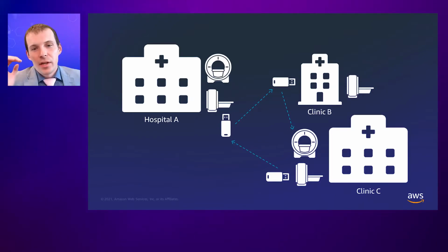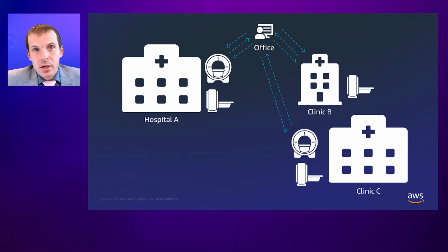Because of that large impediment of time, the threshold for me for making a change is actually pretty high. So we make fewer changes than we'd like to make because of this current situation. With the solution that Yaxi from GE just described, the need to physically go site to site, the need to stop that site from scanning patients because I need to get on the scanner to program it, and the need for that site to stop earning any revenue, those needs evaporate. I can sit in my office and manage all of these scanners as shown in this figure.